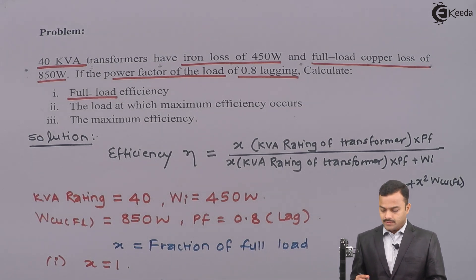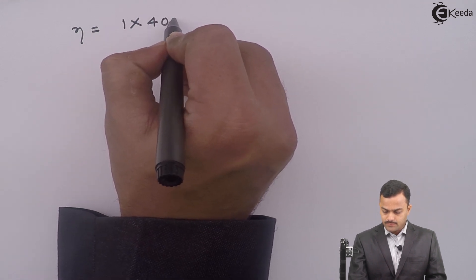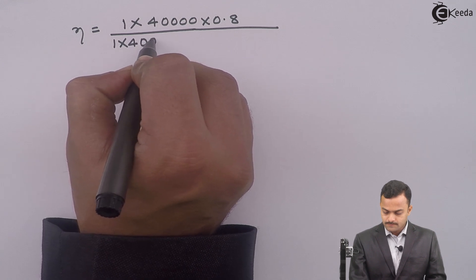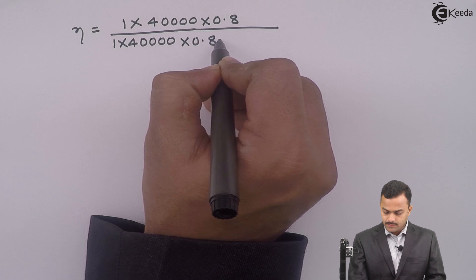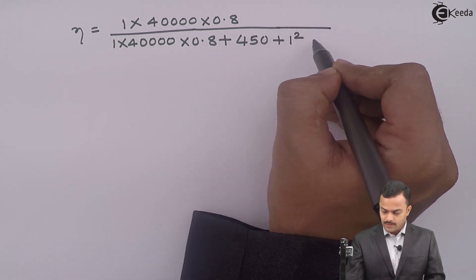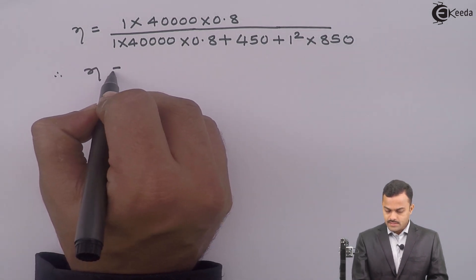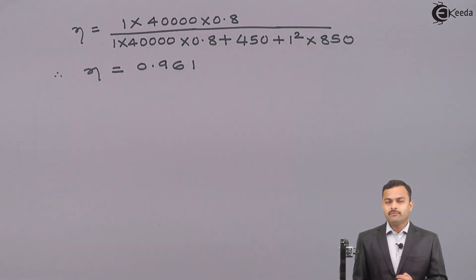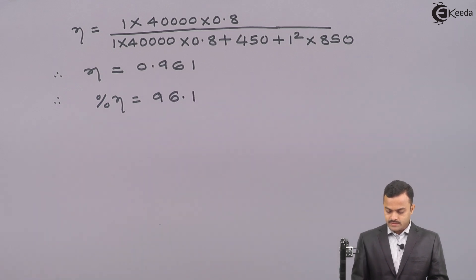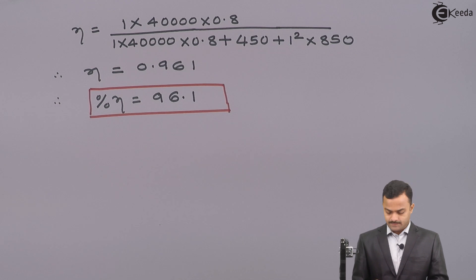Substituting for full load efficiency: x is 1, kVA rating is 40,000, power factor is 0.8, divided by 1 multiplied by 40,000 multiplied by 0.8, plus iron loss 450, plus 1-squared multiplied by copper loss 850. Solving this gives efficiency equal to 0.961, or in percentage, 96.1%. So the full load efficiency is 96.1%.